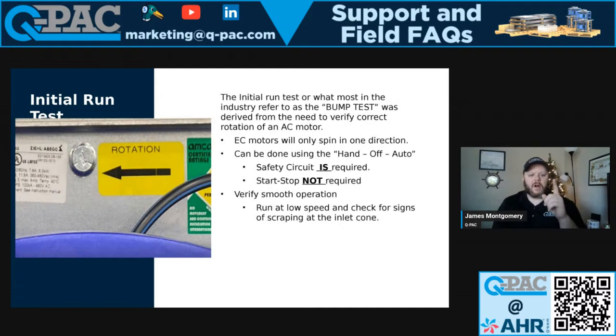I put a sticker on there. Our fans have a sticker that says rotation goes in this direction, right? That's counterclockwise if you're looking at the fan from the outlet side, where the air is blowing at you. Again, EC motors will only spin in one direction, the direction they're told or programmed to go in. They can be programmed otherwise, but that's not how the Q-PAC fan system works. We don't program them to go the other direction. It specifically relates to the characteristics of the wheel and the blade and how it's going to move air.